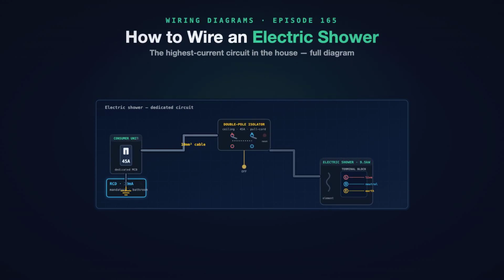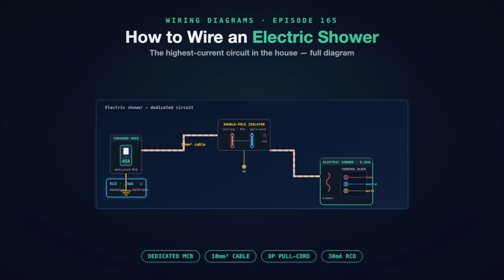This is how to wire an electric shower, the highest current circuit in the whole house. One dedicated breaker at the consumer unit. One heavy cable. A double pole pull cord isolator on the ceiling. And the shower unit itself. No plug, no socket. A fixed, dedicated circuit all its own. Get the breaker, the cable, and the isolator sized right, and it is simple. Get them wrong, and it overheats. Let me walk the whole circuit.